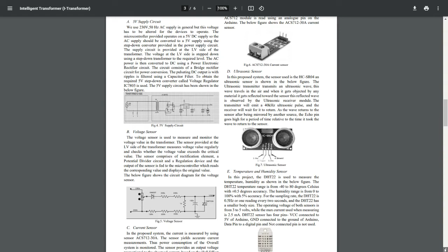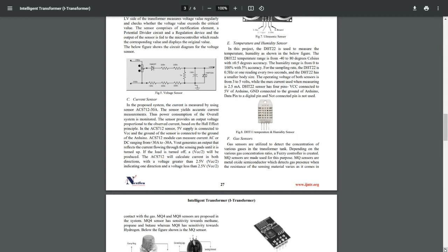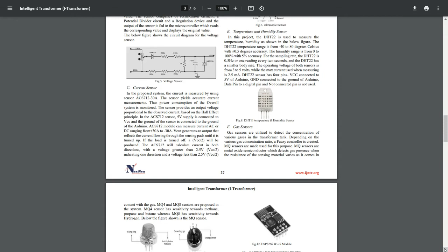In the proposed system, current is measured using sensor ACS712 30 ampere, which yields accurate current measurements. The ultrasonic sensor used is the HCSR04. The DHT22 is used to measure temperature and humidity. Gas sensors are utilized to detect the concentration of various gases in the transformer tank, and depending on the gas concentration ratio, a fuzzy controller is created. MQ4 and MQ8 sensors are proposed in the system, where MQ4 has sensitivity towards methane, propane and butane, while MQ8 has sensitivity towards hydrogen.